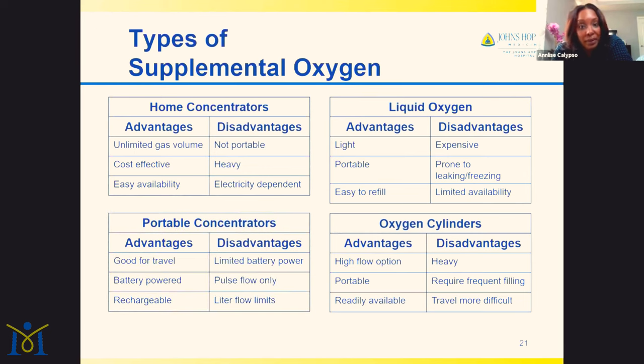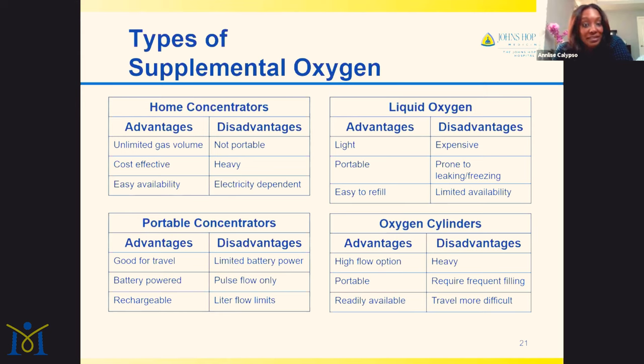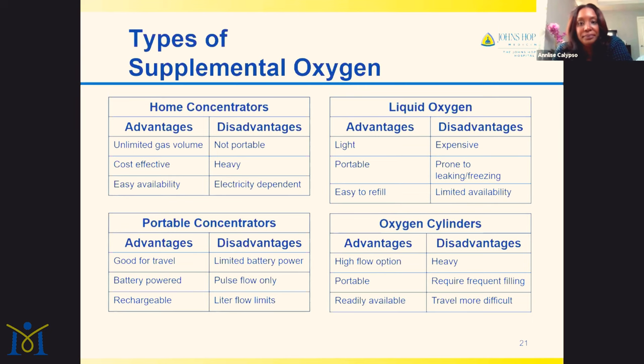The most popular of the four types are portable oxygen concentrators. Most people have seen a commercial for some sort of device. The advantages are they're great for travel, battery operated, and rechargeable. Disadvantages are limited battery power, they only deliver pulse flow oxygen, they have liter flow limits, and they can be cost prohibitive.